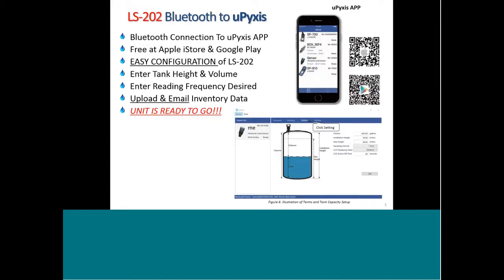Can it work simultaneously with wired and Bluetooth? Yes, it can. If you wire it directly to a controller, it will be powered by the controller, and it will return a 4 to 20 signal to the controller, but you can still configure the device to output a Bluetooth signal so that as a service technician or an account manager, as you're walking by the tank or taking a delivery, you can pull the probe on your phone and see real-time inventory, but also upload historical data.